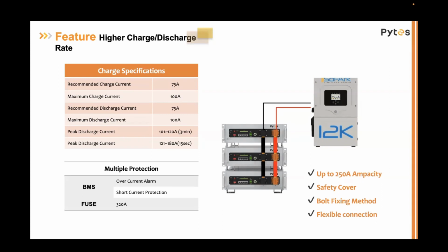We have a continuous charge and discharge of 75 amps, and with a firmware update to the battery system, this allows us to actually charge and discharge 100 amps. So we can pair that up and release every battery to have 100 amps DC into the system. We also have some peaks to note: within 3 minutes, our batteries can peak up to 101 to 120 amps DC, and within 15 seconds, powering a motor or other DC rated engine, these batteries can reach 120 to 180 amps DC.